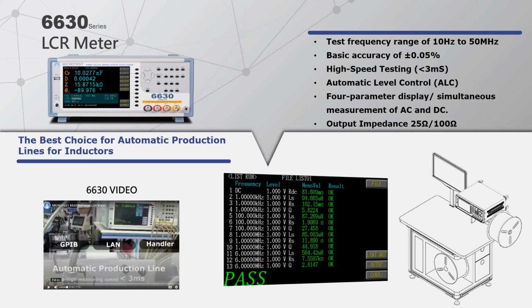The 6630 series LCR meter is a high-frequency, high-speed LCR meter with a test frequency range of 10 Hz to 50 MHz. Basic accuracy reaches ±0.05%, and it offers rapid measurements in as fast as 3 milliseconds. It features automatic potential compensation, simultaneous AC and DC measurements, and a switchable output impedance of 25 ohm or 100 ohm.